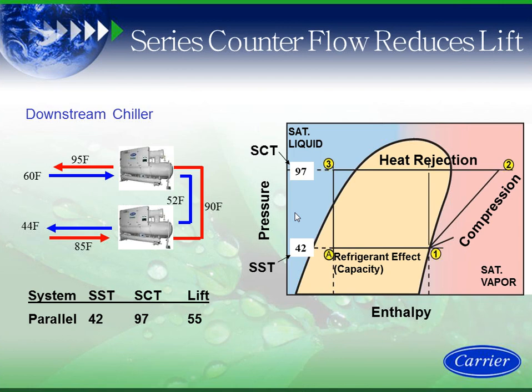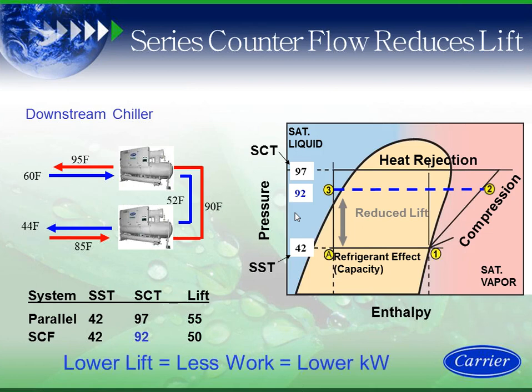So if I look at a parallel chiller plant, I have 2 parallel machines, and they always have to deliver 44 degree water out of each machine. And I always have 85 entering and 95 leaving on a design day on those parallel machines. On a series counterflow, on the downstream chiller, I still have 44 degree leaving, but I have 92 degree saturated condensing temperature or 90 degree leaving. So I actually save 5 degrees of lift versus a parallel chiller plant with this application. When I reduce lift, I save energy and I save kW on the system itself.